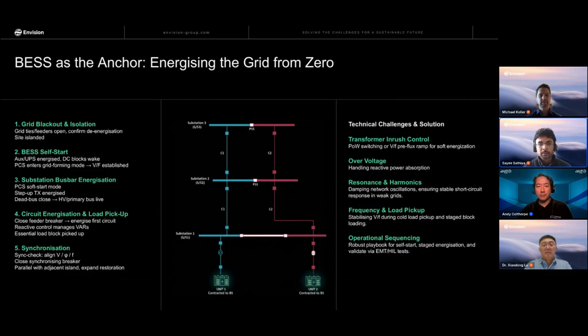In this slide, I'm going to explain the black start sequence, on how we are going to use a BESS as an anchor generator or a primary service provider. So in a typical condition, this is a bottom-up approach. Basically, we are going to energize the grid from zero. We need to operate the BESS as anchor generator when there is a blackout condition on the grid, and everything is isolated and open. When there is a blackout, your BESS system is going to shut down on the loss of mains, and all your substations and everything will be in a de-energized state, and you will be islanded.